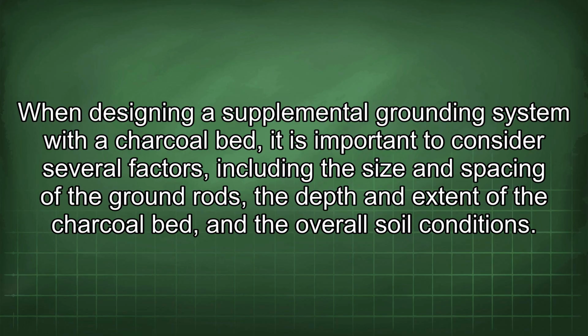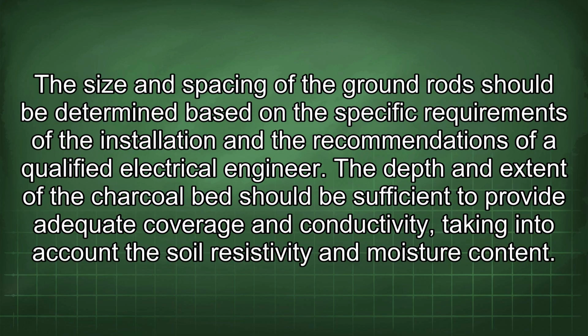When designing a supplemental grounding system with a charcoal bed, it is important to consider several factors, including the size and spacing of the ground rods, the depth and extent of the charcoal bed, and the overall soil conditions. The size and spacing of the ground rods should be determined based on the specific requirements of the installation and the recommendations of a qualified electrical engineer. The depth and extent of the charcoal bed should be sufficient to provide adequate coverage and conductivity, taking into account the soil resistivity and moisture content.